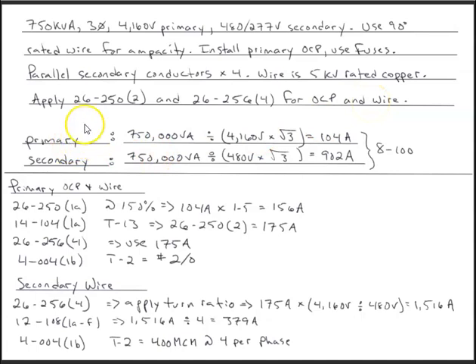So just as we've done in first level, the system is the same. We're just changing a couple elements of the calculation here. So the primary, we take 750,000 volt amps, and that's kVA. So 750,000 volt amps divided by 4160 times the square root of 3. Because we're dealing with three-phase, we have to apply the square root of 3. So we end up with, on the primary, 104 amps.